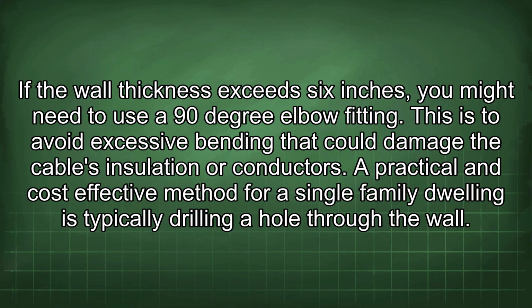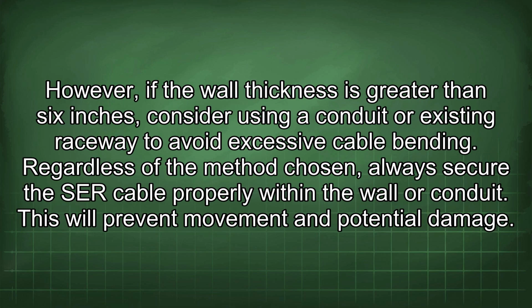A practical and cost-effective method for a single-family dwelling is typically drilling a hole through the wall. However, if the wall thickness is greater than 6 inches, consider using a conduit or existing raceway to avoid excessive cable bending. Regardless of the method chosen, always secure the SER cable properly within the wall or conduit. This will prevent movement and potential damage.